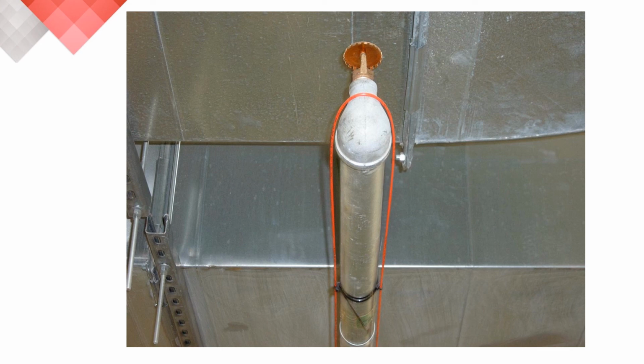Occasionally, however, there's not another branch line to turn toward. In this case, the detector should have cable ties at each end of the piping, allowing it to create a minimum of 5-inch detector loop in the open air. This image certainly violates the 2.5-inch bend radius and may have mechanically damaged the detector.